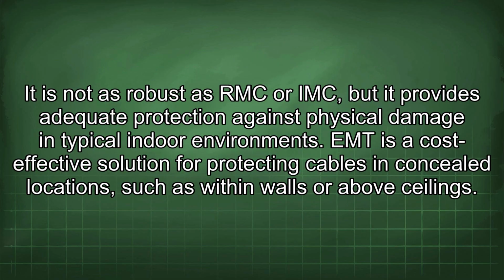It is not as robust as RMC or IMC, but it provides adequate protection against physical damage in typical indoor environments. EMT is a cost-effective solution for protecting cables in concealed locations, such as within walls or above ceilings.